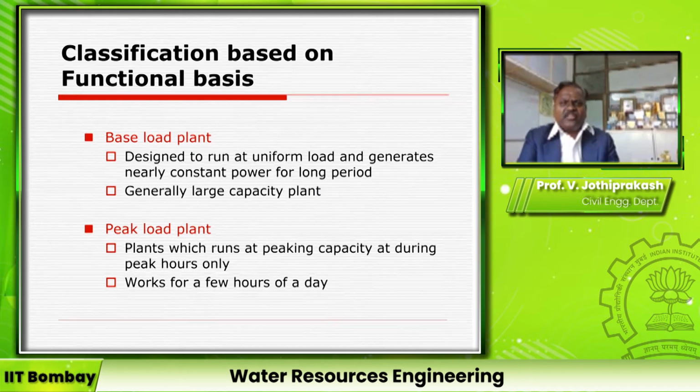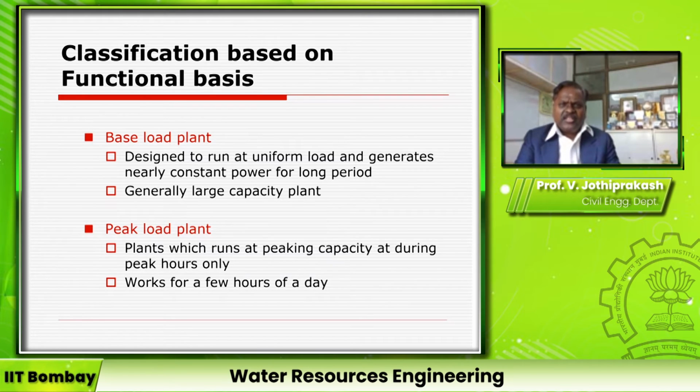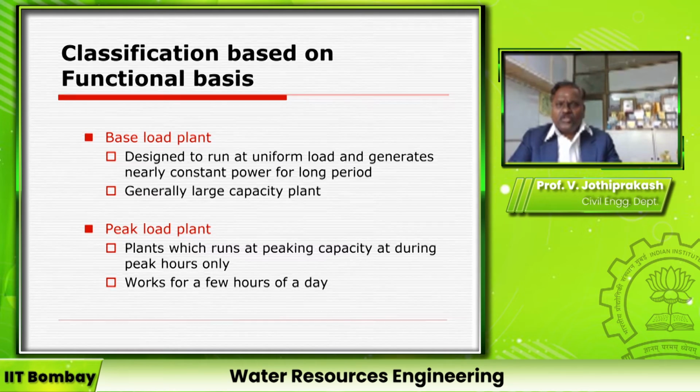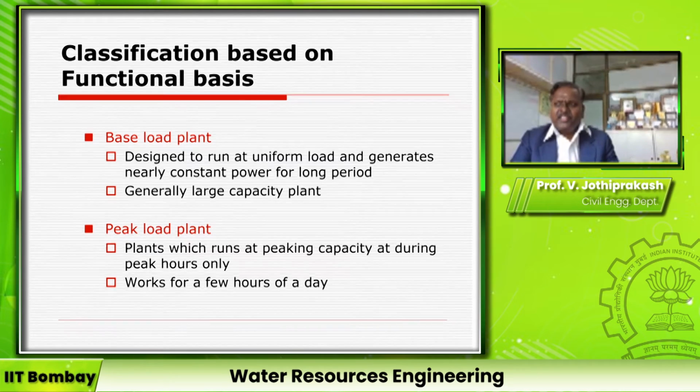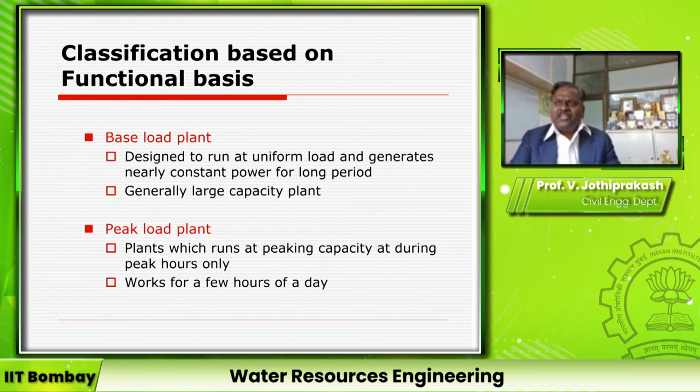Then based on function: what purpose are you constructing that powerhouse for? As we have seen, storage power plants are mainly peak load plants. That means whenever there is a peak power requirement, you just start the hydroelectric power station, because a hydroelectric plant can be started in a few hours and closed in a few minutes. So you don't need a large starting time and large closing time like thermal and nuclear power plants. It is like a switch on and switch off. That is why a hydroelectric power plant can be constructed as a peak load plant.